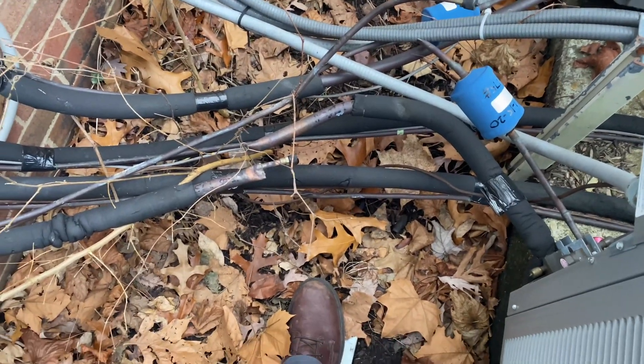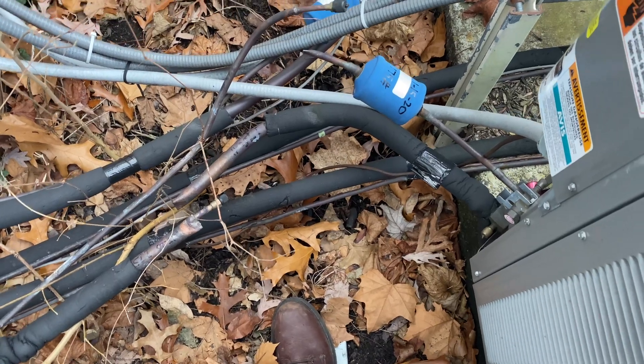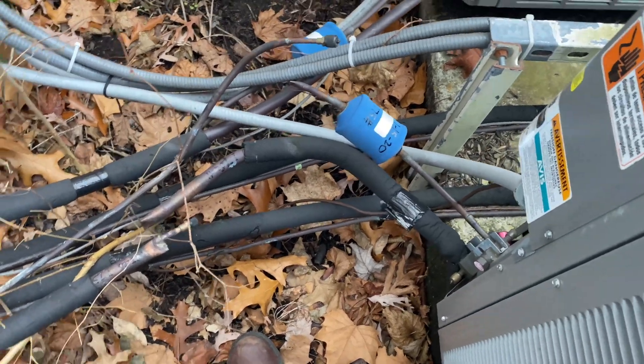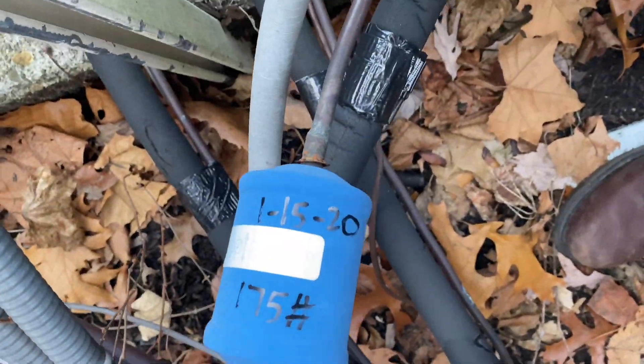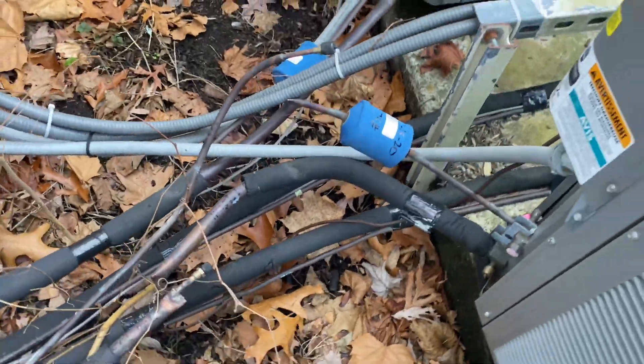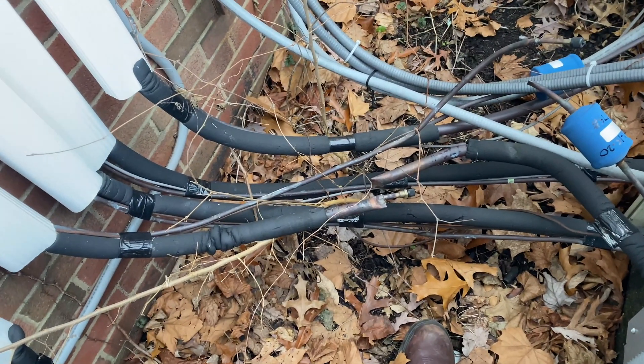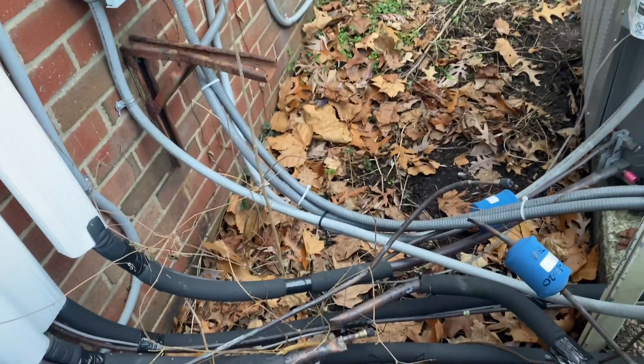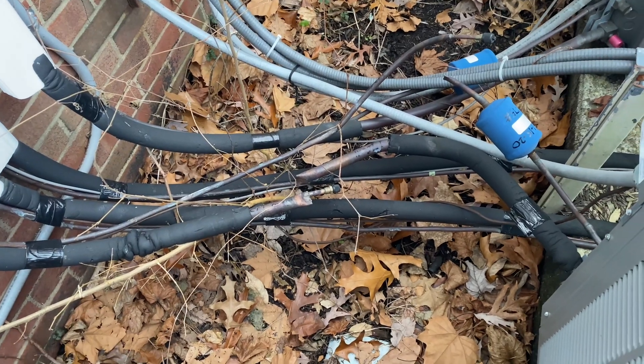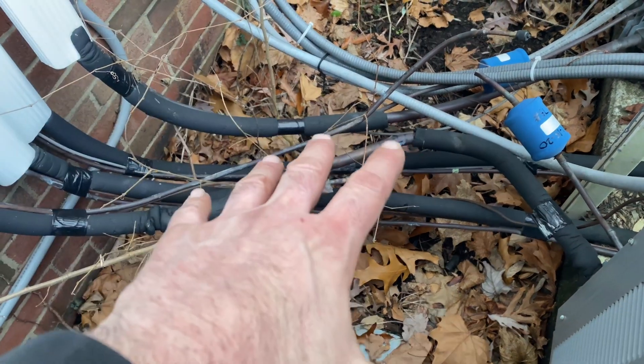You'll come back in a couple days, and when you come back you'll know if it's leaking or not. Somebody installed the dryer — I'm guessing it was installed around 2015 or 2020. A lot of people use electronic leak checkers, but sometimes electronic leak checkers just won't find it, bubbles won't find it — it's so minute. This method will find it.